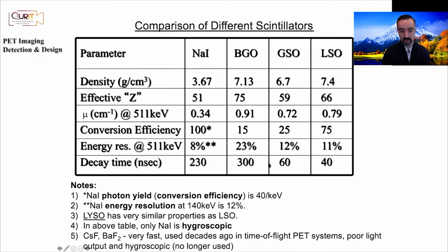And you can sort of see also that it has a very good small decay time. And that means that there's less dead time happening, because it takes you a small amount of time to process one gamma ray, then you're ready for the next gamma ray and then the next gamma ray.